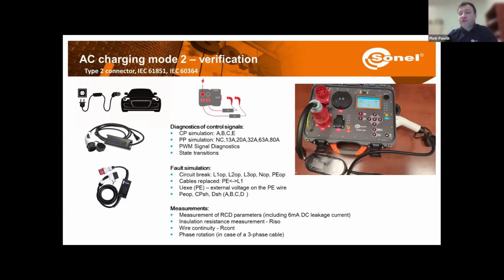As per diagnostics, we need to check different methods. So the control pilot, different states A, B, C, or E, simulating no connection, car connected without charging, charging, or error. We also can check for different levels of currents and perform signal diagnostics for the control pilot and transitions through different states. We can also simulate faults, so breaks in different wires, replaced cables, voltage on PE, or fault simulations in a case of communication.